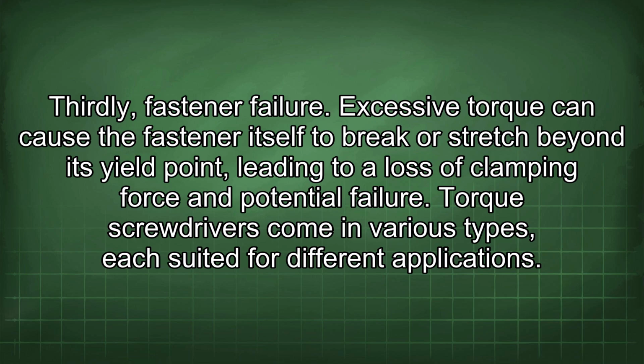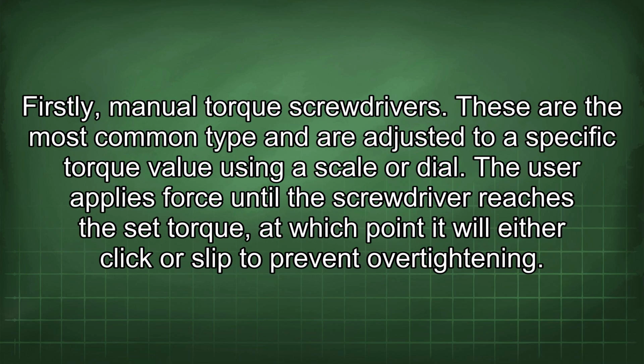Torque screwdrivers come in various types, each suited for different applications. Firstly, manual torque screwdrivers. These are the most common type and are adjusted to a specific torque value using a scale or dial. The user applies force until the screwdriver reaches the set torque, at which point it will either click or slip to prevent over-tightening.